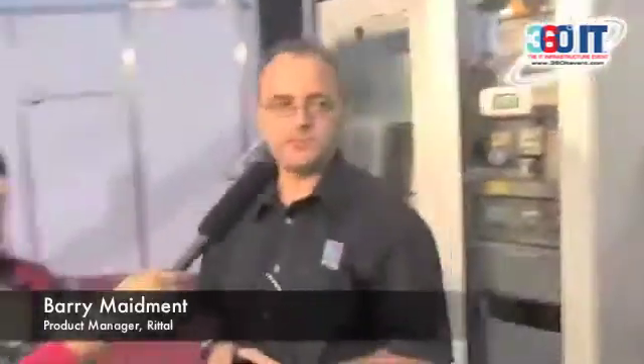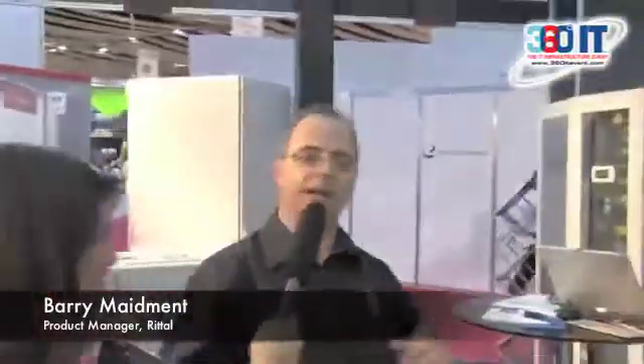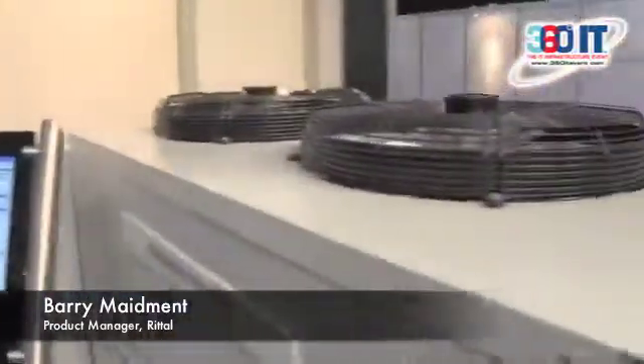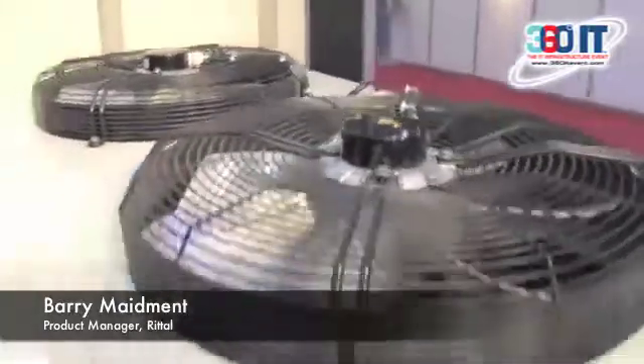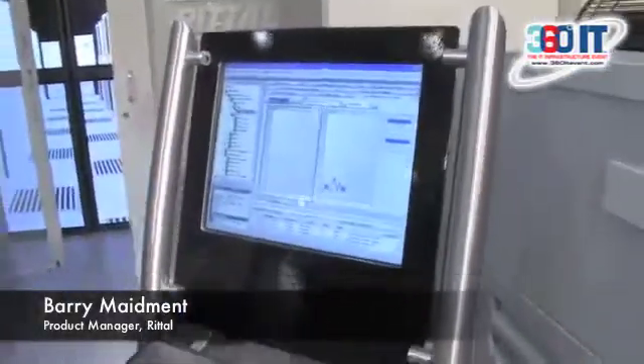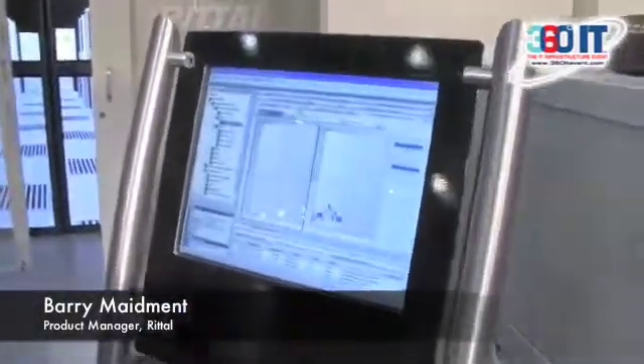On the outside, we actually have the chiller. The chiller is where we produce the cold water that is then delivered to the CRAC system and also the LCP. So the chiller system is here, and again that is situated outside, and using devices such as free cooling, we're able to reduce the overall energy consumption down to around about 46%. So again, it just makes it a lot more efficient, and then the whole system is tied in using a software package that makes the whole modules work together.